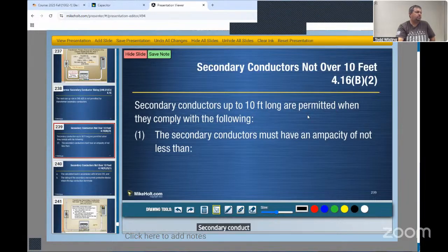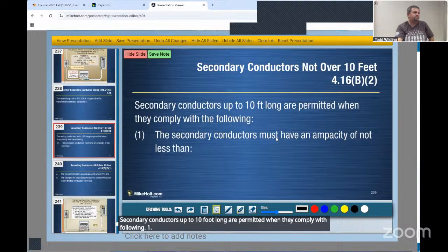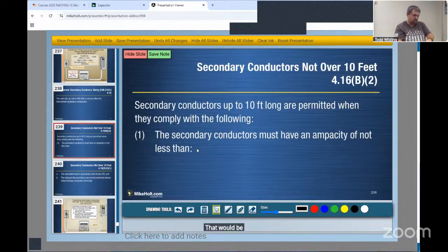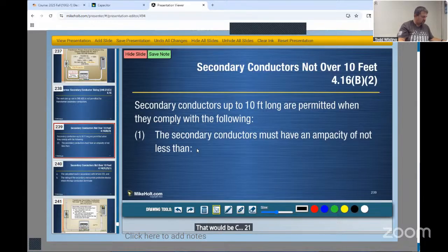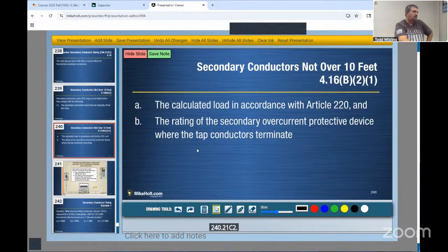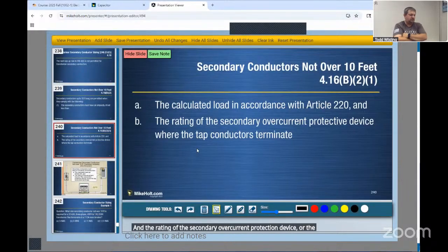Secondary conductors up to 10 foot long are permitted when they comply with the following. 1, the secondary conductors must have an ampacity of not less than, that would be 240.21(C)(2), right out of the code book, A and B: the calculated load in accordance with Article 220 and the rating of the secondary overcurrent protection device where the tap conductors terminate.